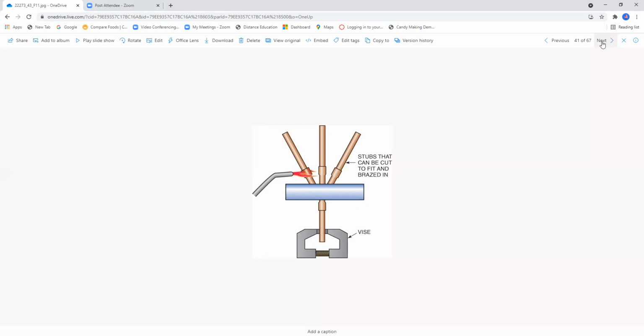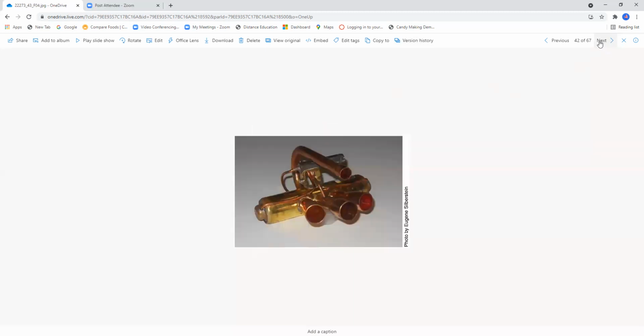That may or may not work. I personally would rather install a reversing valve as it comes from the manufacturer to the existing piping arrangement inside the heat pump. It's harder, but if you protect that reversing four-way valve, you should not have any problems. But the critical issue here is putting a heat sink here to prevent that heat from the torch from affecting the internal Teflon seals and all the things that are inside of this four-way reversing valve. Very critical issue. This is what a four-way reversing valve looks like from the manufacturer.